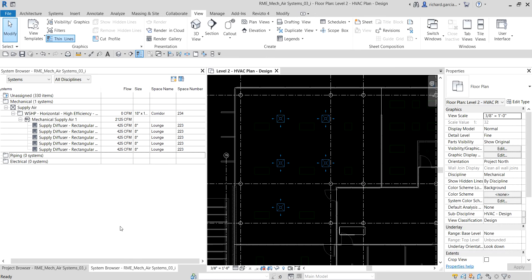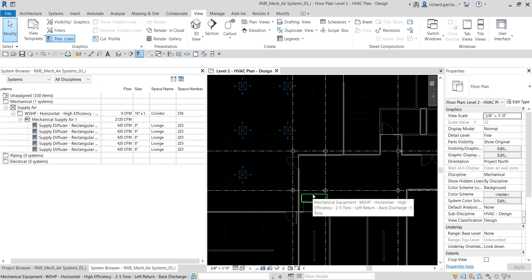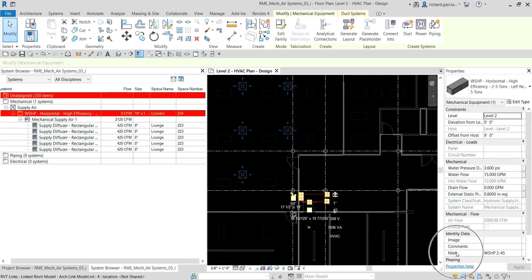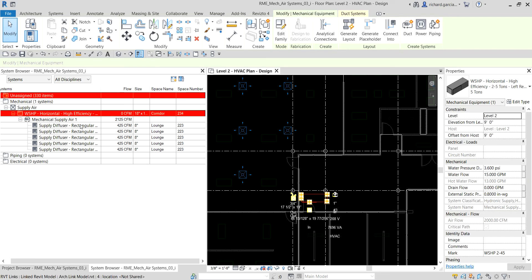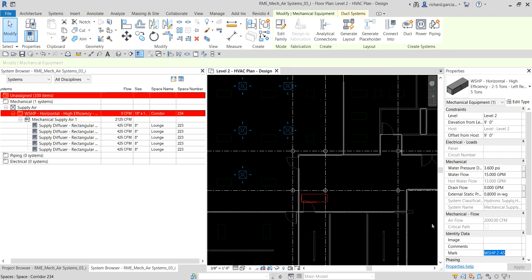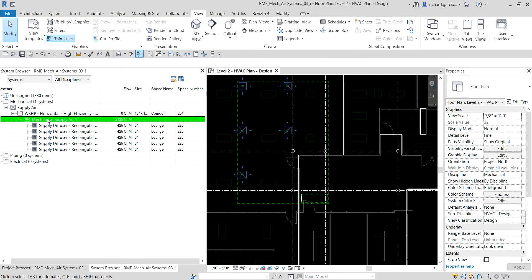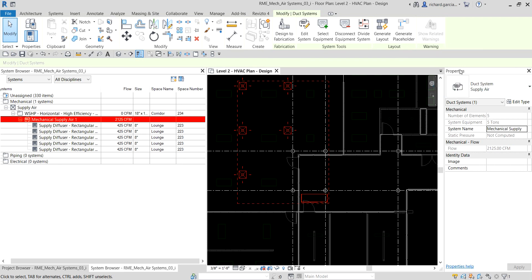To rename the system based on the equipment feeding the diffusers, select the equipment and find the 'Mark' field in its properties. Copy that mark value with Ctrl+C. Then click the system, go to its properties, find the 'System Name' field, delete the existing name, and paste the mark name with Ctrl+V. Click Apply to confirm the new name.